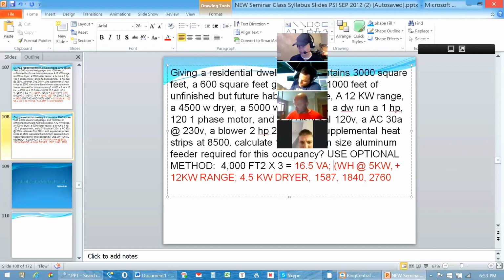Okay, so 16.5 plus the 12 for the range, plus the 4.5 for the dryer, plus the water heater, which was 5, plus the 3 motor loads gives us 1,587 plus 1840. Stop me if somebody's already got this answer. All right, I've got 44,187. Anybody got anything different? I got the same thing. Okay, that's a good sign then. 44.187 kVA, or if you're doing it in volt-amps, it'd just be 44,187.